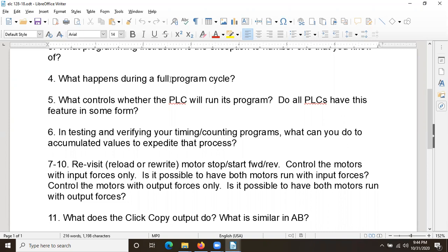That's what happens during a full program cycle. There's 5 steps. Once it updates its outputs, it goes around and starts back on step 1. It goes back around and checks its inputs. And when your scan cycle is like 7 milliseconds, this is happening every 7 thousandths of a second. It's doing all 5 steps. So it's just incredibly fast.